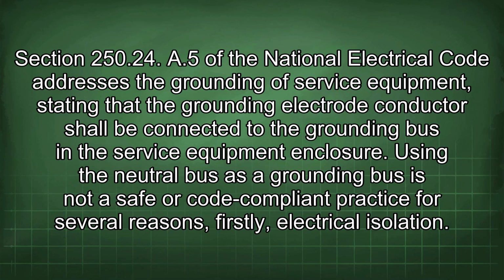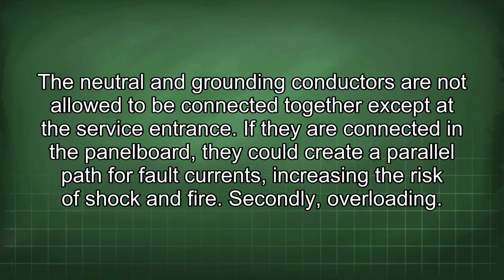250.24(A)(5) of the National Electrical Code addresses the grounding of service equipment, stating that the grounding electrode conductor shall be connected to the grounding bus in the service equipment enclosure. Using the neutral bus as a grounding bus is not a safe or code-compliant practice for several reasons. Firstly, electrical isolation. The neutral and grounding conductors are not allowed to be connected together except at the service entrance.